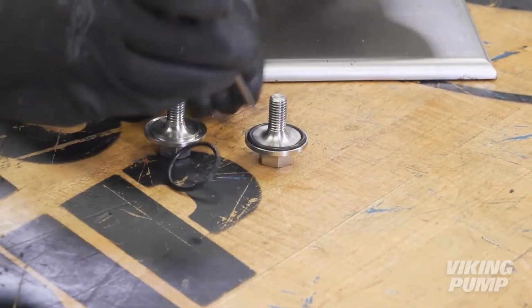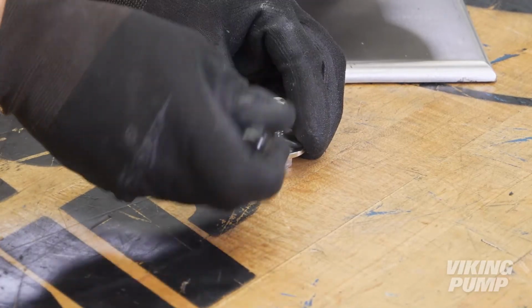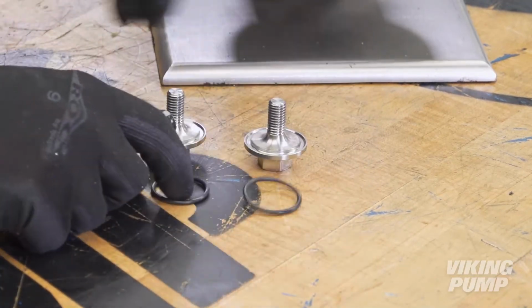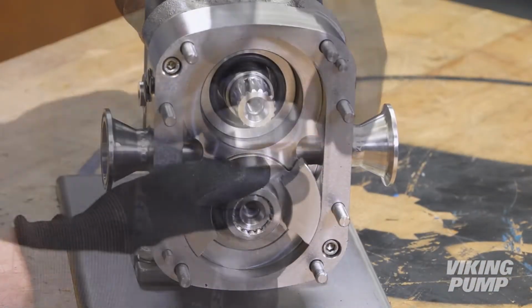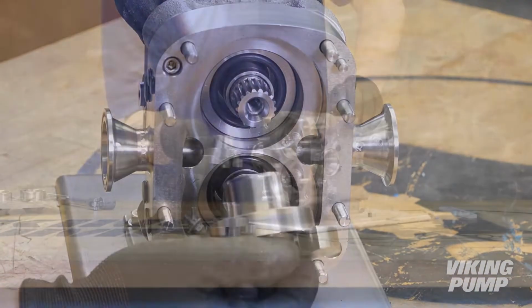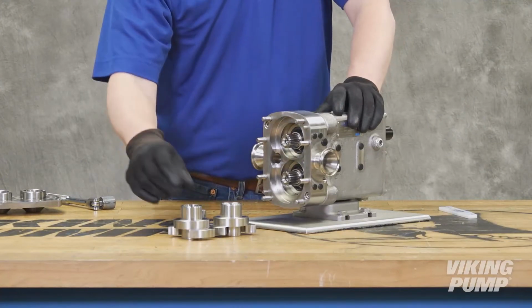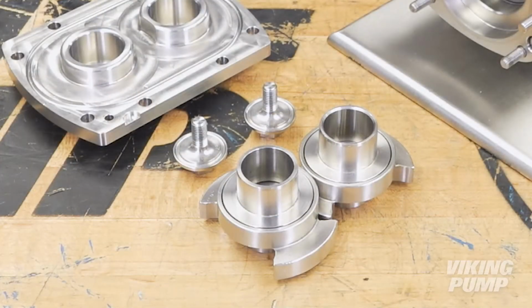Remove the rotor retainer O-rings. Remove the rotors from each shaft. Keep track of the position for each rotor, as each will need to be returned to the same position when reassembled. Place the rotors on the bench, seal side up.